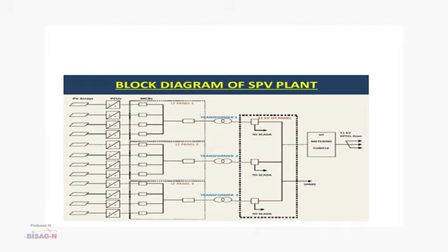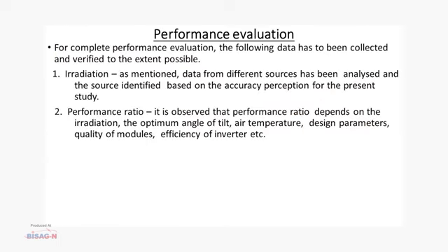On the left hand side modules are shown in arrays which are connected to string monitoring boxes using DC cables. These cables are connected to an inverter which converts DC into AC. 440 volt is generated at the output of the inverter. It is connected to a step-up transformer. 400 volt AC is stepped up to 11 kV, 11,000 volt, which is connected to breakers. This power is taken to the main receiving station through HT cable and it is either exported or imported through the net metering system.